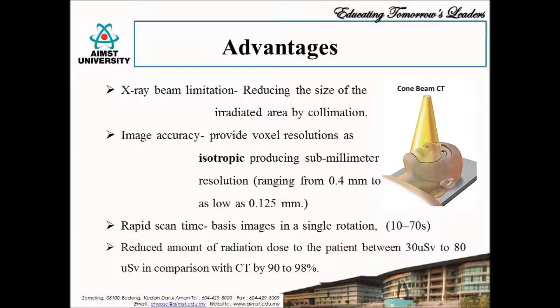CBCT includes various advantages over other three-dimensional imaging modalities, certified by various studies. Regarding X-ray beam limitation, reducing the size of the irradiated area by collimation — that is, choosing a particular FOV of the primary X-ray beam to the area of interest — minimizes the radiation dose. Regarding image accuracy, all CBCT units provide voxel resolution that is isotropic, equal in all three dimensions, whereas in CT these are anisotropic. This produces sub-millimeter resolution ranging from 0.4 mm to as low as 0.125 mm.